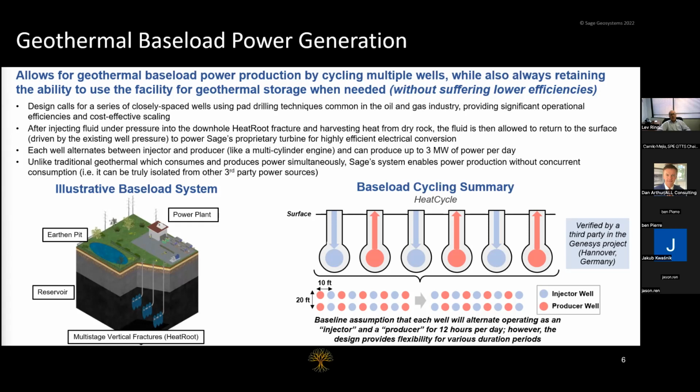They need to be 200 feet apart, so as not to thermally affect each other in 30 years. Thermal conductivity of rock is very, very low. So the drawback is it's very difficult to harvest heat because you cool fast, but also fractures or wells don't thermally affect each other if there is even a very small separation.